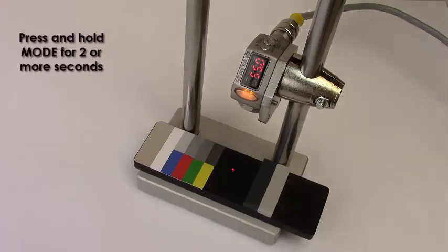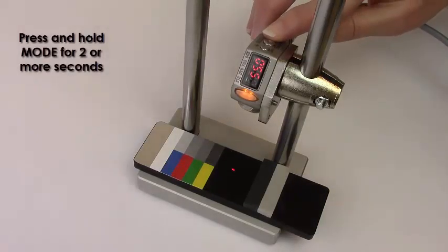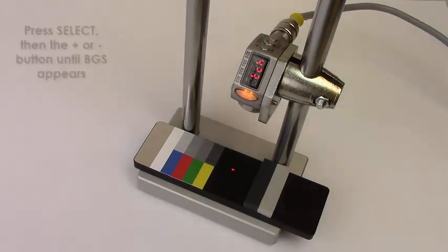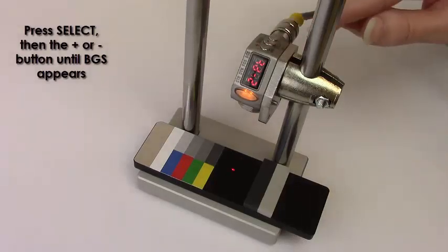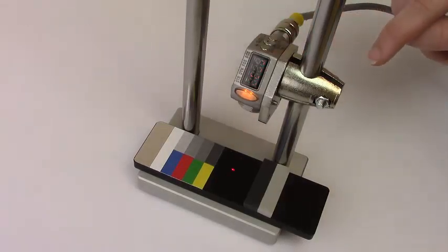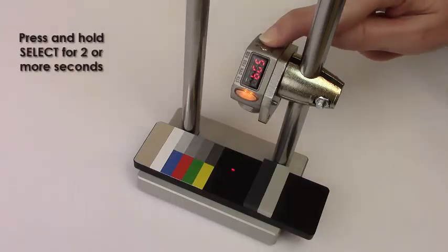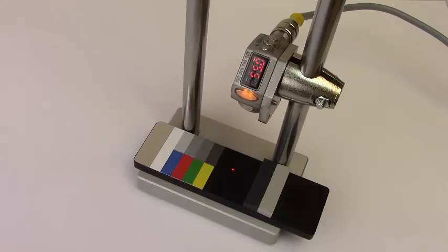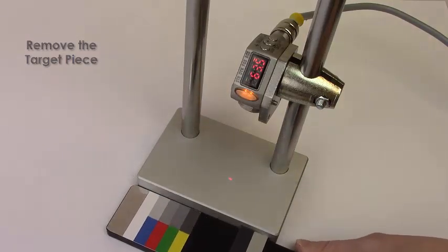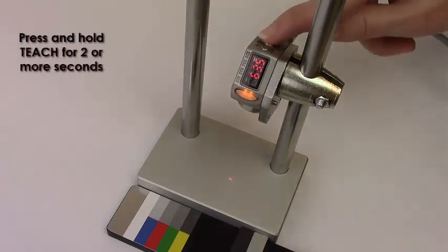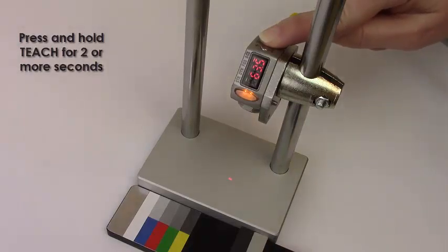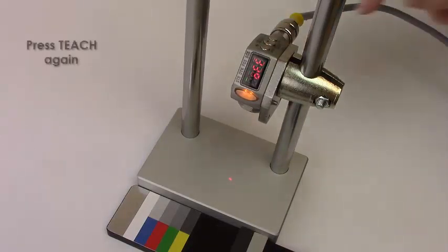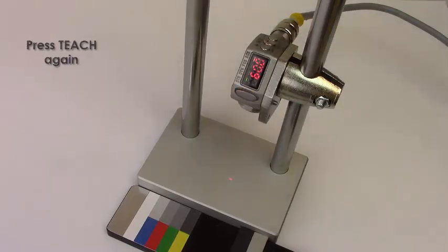Press and hold mode for two or more seconds. Press select, then press the plus or minus button until BGS appears. Press and hold select for two or more seconds. The display flashes and returns to run mode. Remove the target piece. Press and hold teach for two or more seconds, then press teach again. The aluminum base is now the zero point.